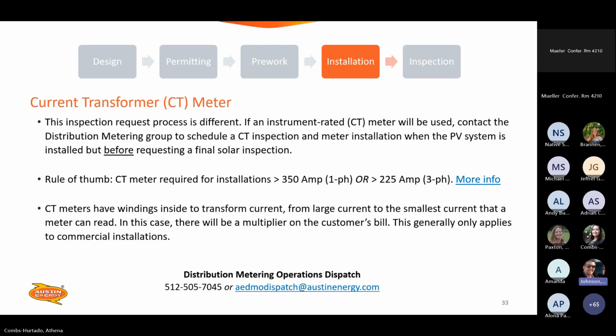So CT meters do have windings inside the transformer to transform current from large current to small current so the meter can read it. In this case, there's a multiplier on the customer's bill, and this generally only applies to commercial installations. Next slide, please.